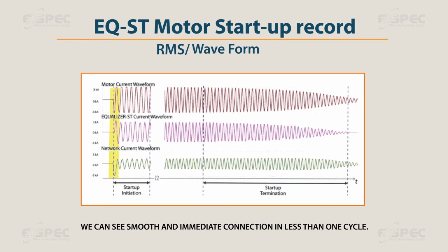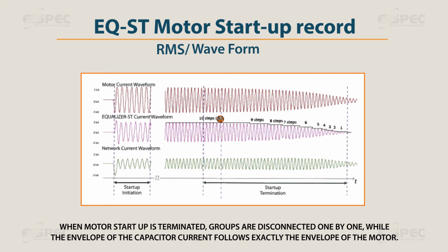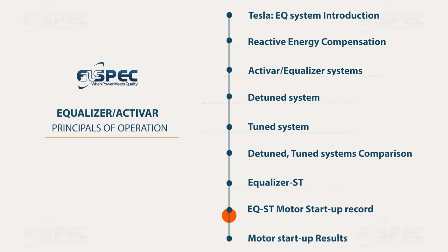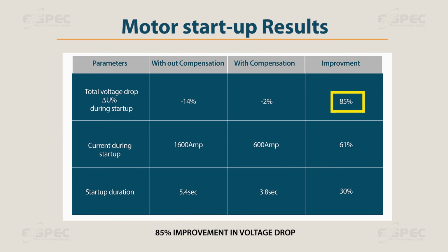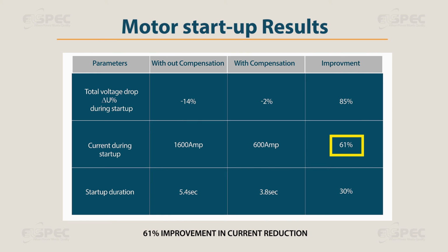We can see a smooth and immediate connection in less than one cycle. When motor startup is terminated, groups are disconnected one by one, while the envelope of the capacitor current follows exactly the envelope of the motor. The results: 85% improvement in voltage drop, 61% improvement in current reduction, and 30% reduction in startup duration.